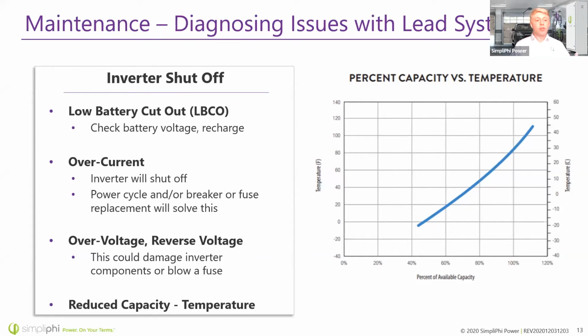Your inverter could have shut off because there was an overcurrent event. In this case, you'll likely have just a switch on the inverter that you can cycle off and back on, and it will often solve that problem. You may have experienced an overvoltage or reverse voltage event if you hook the battery up in the wrong direction, or if there was just too much voltage on the battery from being overcharged. This could actually damage your inverter. Maybe it blows a fuse, hopefully not.